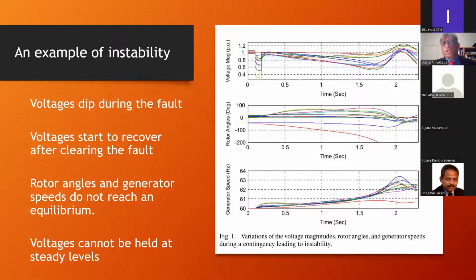Then the fault is cleared and the voltages, at least temporarily, recover close to the original values. But in this example, it cannot hold these voltages for long. It starts sliding down, and toward the end you can see some oscillations and the system going unstable. Rotor angles and generator speeds are also shown in this figure. So this is an unstable situation - transient instability or rotor angle instability.